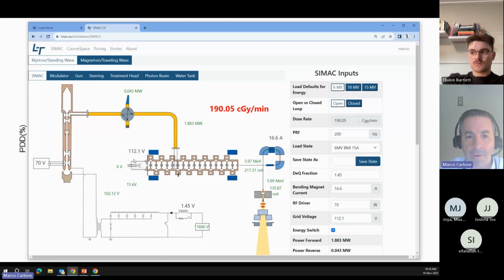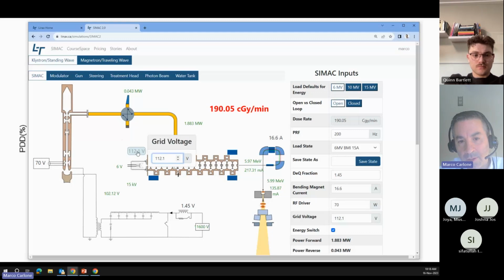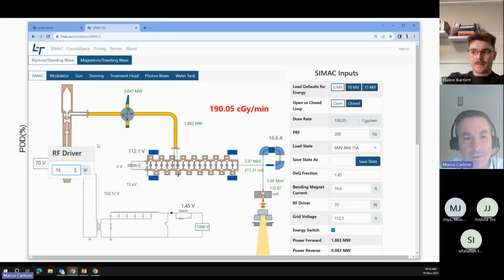We have a bunch of numbers that come up on our screen, and these numbers all represent different things that configure the machine. In order to keep the interface simple, we left the numbers there without labeling them. But if you hover over a number, it tells you what that is. This number here represents the grid voltage on the gun, and you can change that if you want to. This number over here represents the RF driver power to the klystron, and this number over here represents the klystron pulse voltage. Some of these numbers are entries, so we can change them. Some of these numbers are results of calculations, or you have to go somewhere else in order to change that.